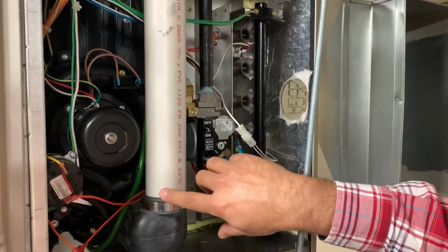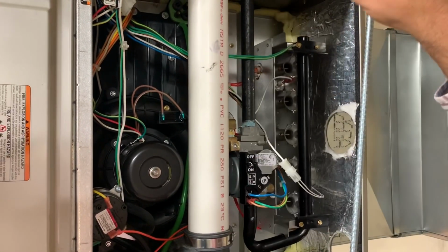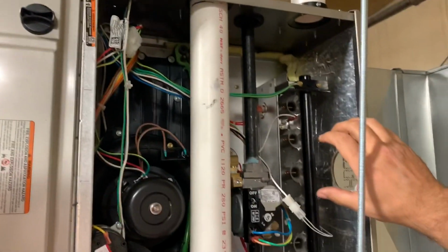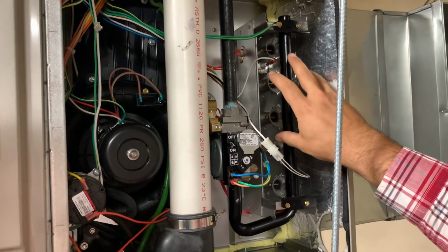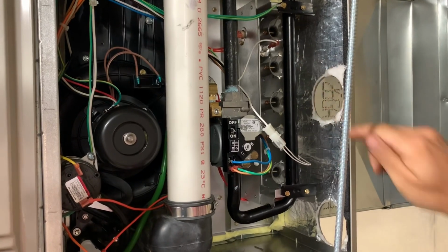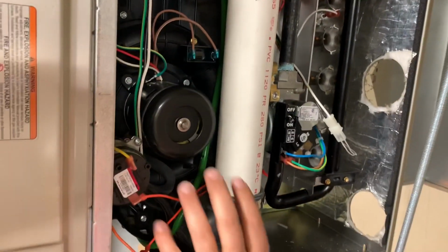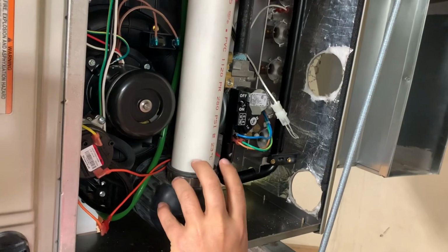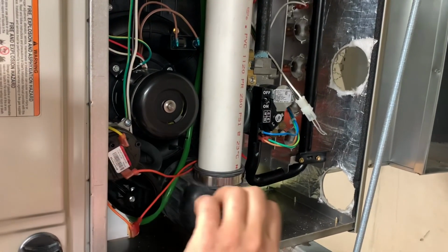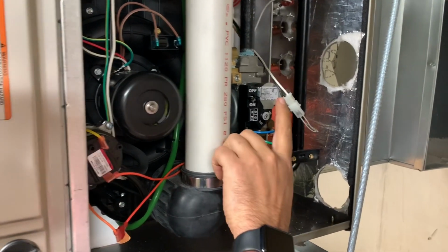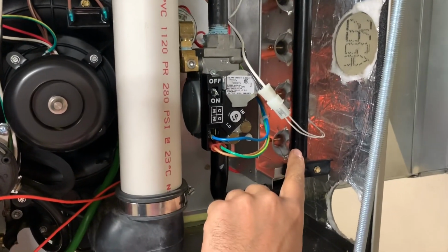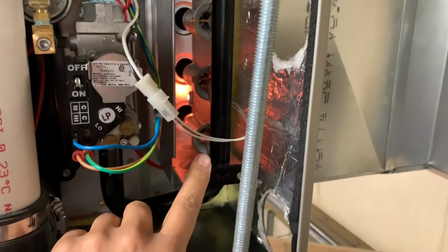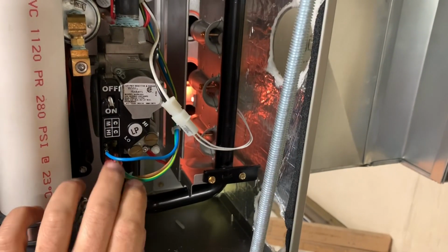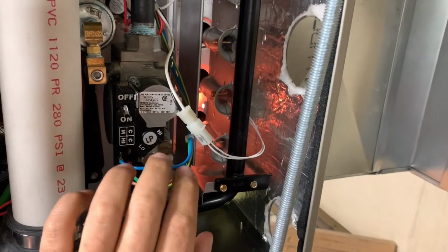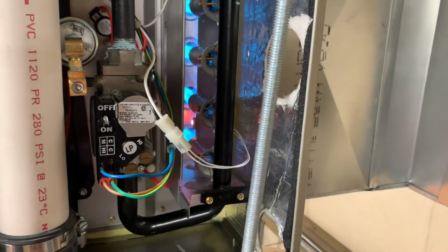So guys, you can hear that inducer fan kick on. That's this thing here, immediately exhausting any air that could be getting pulled through these tubes. This is a sequence of starts: this thing starts up and notifies the furnace through the pressure switches, so now it moves to the next step, the glow plug comes on, you see that? Then you'll hear the gas valve click, immediately ignition.